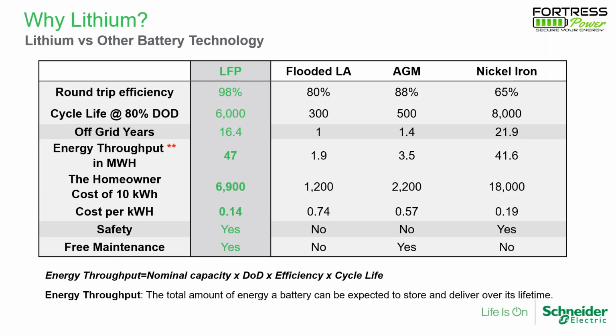Next slide. And here we come down to a little bit more detail on the numbers. We're trying to quantify what we tell our customers and the installers. On round trip efficiency, the lithium phosphate battery is at 90% or above. In a traditional system, the maximum is 88%, and most of them stay at 80% or 75%. The life cycle at 80% depth of discharge is 6,000 cycles, slightly lower than nickel iron. However, the cost is much cheaper than that, and it's much better than AGM or flooded lead acid. This makes the off-grid life up to 16.4 years, and the total energy output will be 47 megawatt hours through its life cycles.